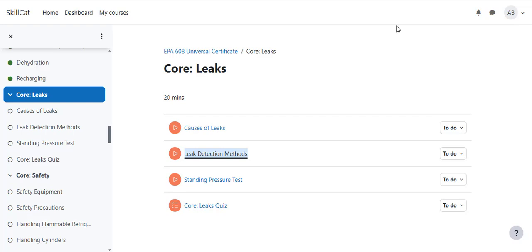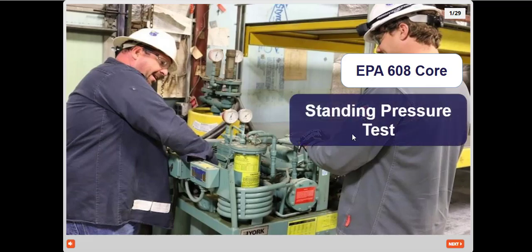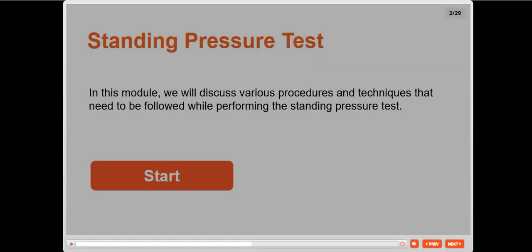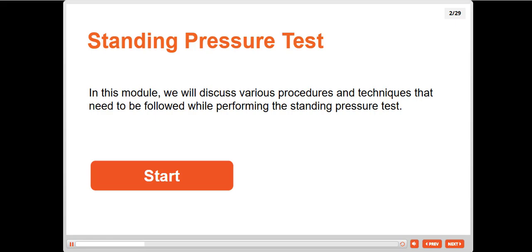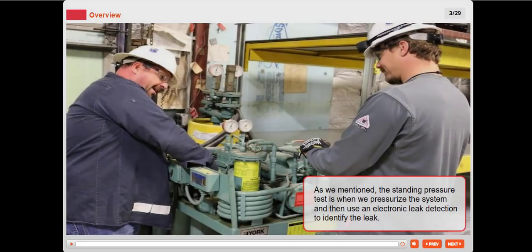Standing pressure test. This is the next and last part of leak testing. In this module, we will discuss various procedures and techniques that need to be followed while performing the standing pressure test. Let's start. As we mentioned, the standing pressure test is when we pressurize the system and then use an electronic leak detector to identify the leak.